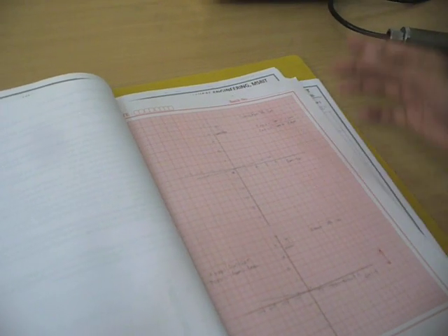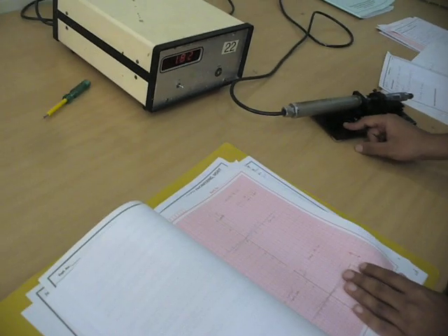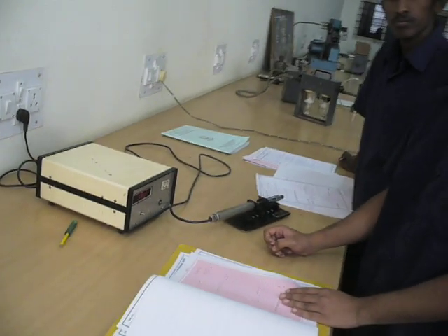We see that as the measured value increases, like 1 mm, 2 mm, 3 mm, our correction also increases, meaning the LVDT becomes less accurate for greater values. And the error is also the same. What is the percentage error? How does the percentage error vary? Our percentage error is also very big. We've obtained a maximum of minus 9.5% and a minimum of minus 8%, which is quite a high value. So we can conclude that this particular LVDT is not very highly accurate.